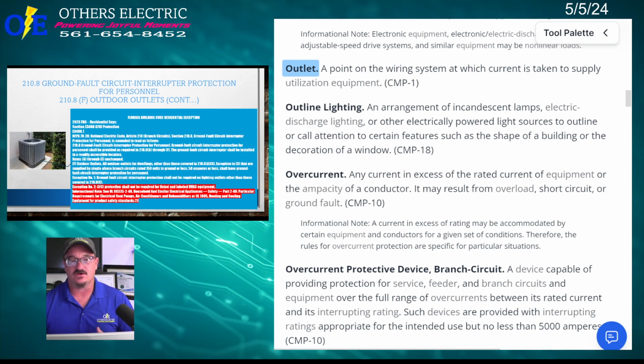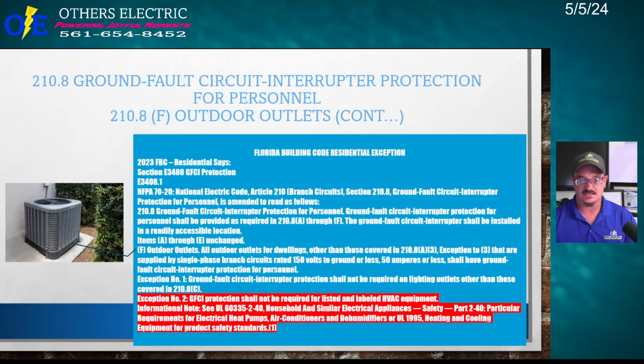Condensing units aren't built to the high standards yet. So I think they've given them until 2026, and they're going to change the way the condensing units are built and manufactured, so they will be able to be installed on GFCI protection without causing tripping. But right now, they're excluded. You don't have to put condensing units or HVAC equipment on GFIs because they're not built to the proper standards that wouldn't trip a GFI. So that's a big change. Just remember that. Outdoor outlets.